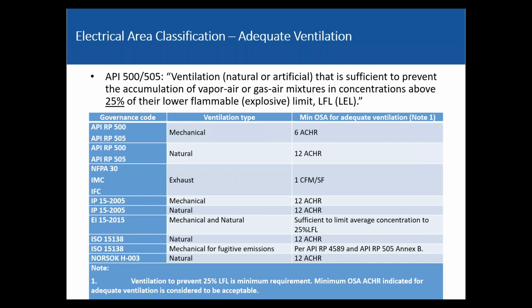What is adequate ventilation? The term gets used a lot. Adequate ventilation by API 500 and 505 is ventilation sufficient to prevent accumulation of gas-air mixtures above 25% of the LEL. That's what we hold on to when we do analysis. I can't remember the LEL numbers, 4%, 15%, it doesn't matter, we have process safety people for that. For methane, that's the process.